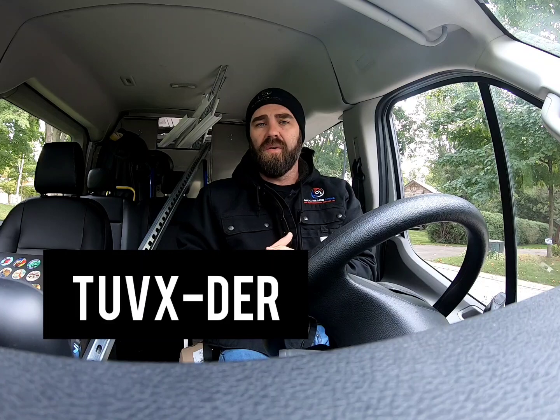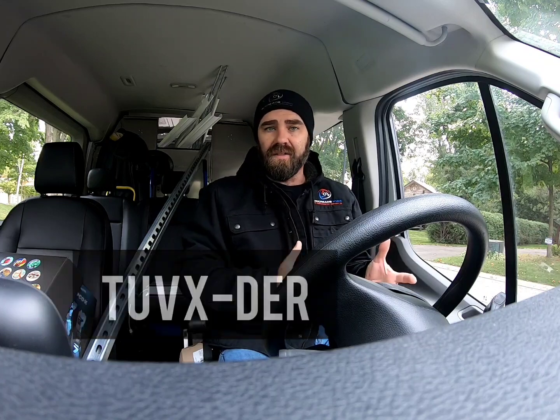So what we're going to do here is install an APCO-X UV light in a residential application. Now I'm going to take you in and show you this, but there's zero room above the coil because what they've done is the coil is raised up and it's at the end of the supply plenum. So there's zero room to install the whole APCO-X right above the coil to decontaminate it. So this model here, and I'll take you inside and I'll show you, comes with a light that is actually remote from the main part of the equipment, and you can remotely wire a light so it's above the coil and still decontaminate it. Let's go inside and I'll show you.